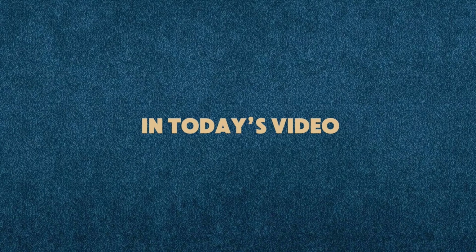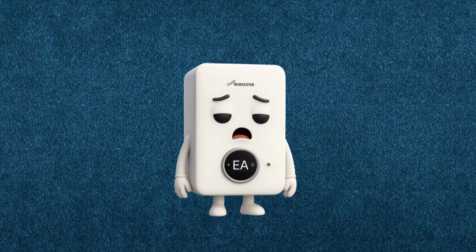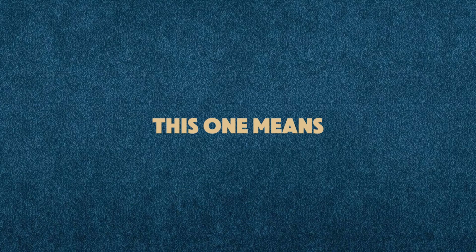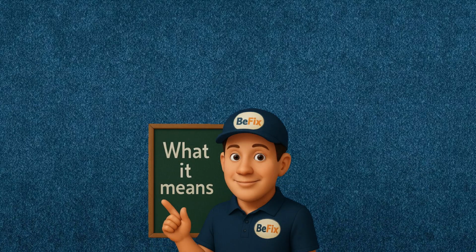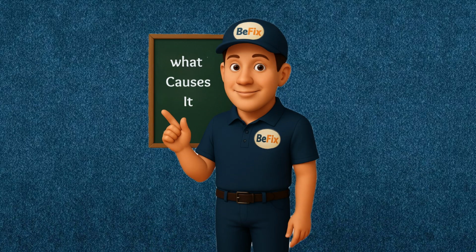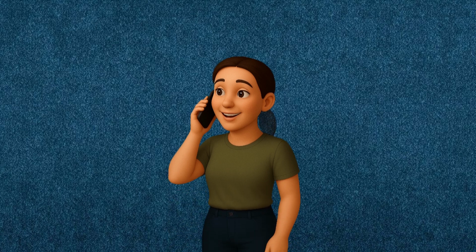In today's video, we're explaining the Worcester Bosch EA error code. This one means your boiler is trying to light, but it can't detect a flame. I'll take you through what it means, what causes it, and what you can safely check before calling a Gas Safe engineer.